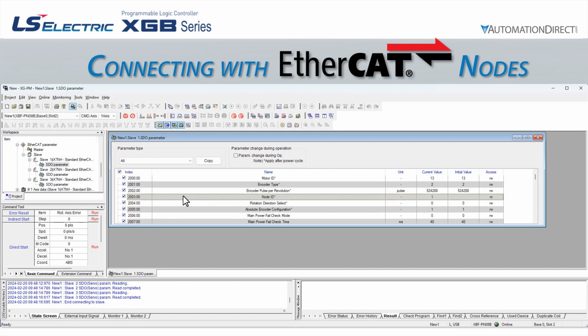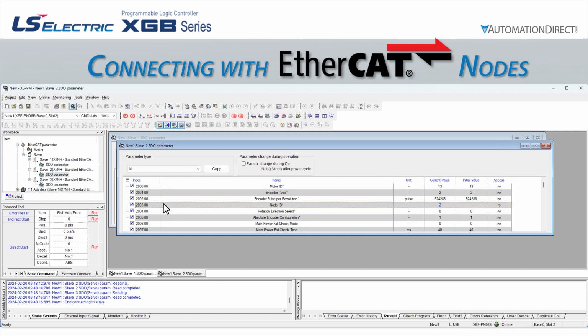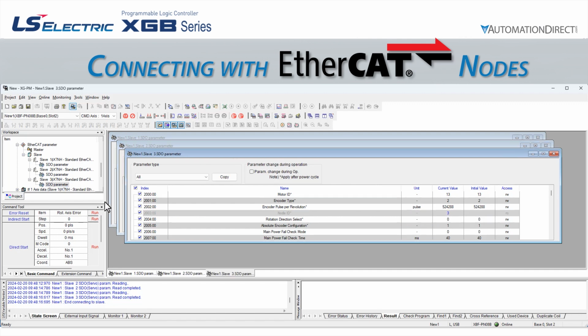We can now look at parameter 2003:00 for slave 1 and see that the node ID is 1. Let's perform this same check for axis 2, and we see that it is node 2, and finally for axis 3, and it is set to node 3. Perfect. The software offers one final feature to help prevent drives being hooked up in the wrong order.